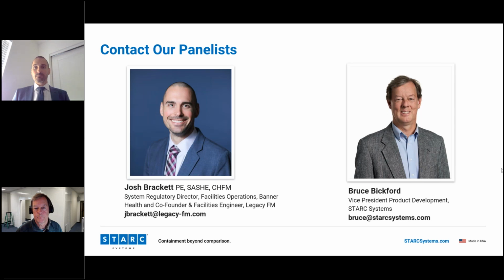Great. Couple more questions for you, Josh. What do you personally like to see on active construction projects? Oh, that's a good one. So I personally like that you're talking to a fire protection engineer, right? I say, personally, if we can have sprinklers, do sprinklers, because a sprinkler system is built to contain that, especially if I'm looking in healthcare and I've got occupants there that are adjacent to it, then I really try to do active sprinkler systems.